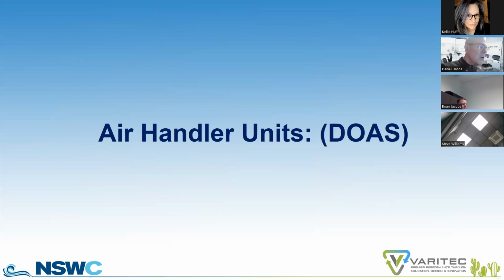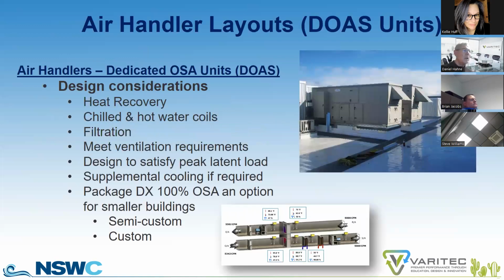These are not just air handlers on a roof. I've been challenged in the past with, well, that's an expensive air handler. Well, you're right. They're not as competitively priced as a conventional medium pressure VAV air handler. Why is that? Well, for one thing, we have to make sure that we're adequately conditioning the outside air. Your dollars per CFM, depending on the size and CFM of the unit, could range anywhere from $10 a CFM to $15 a CFM on a custom unit. You can also use a semi-custom design that offers a lower price point, if you go with a semi-custom unit by the various manufacturers out there.